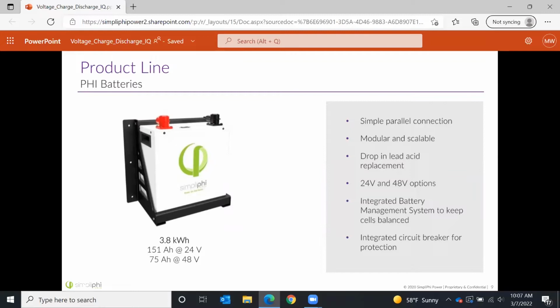It's compatible with a wide range of existing equipment, even older equipment like Midnight charge controllers, Outback charge controllers, even those FX or MX charge controllers, very simple devices that don't need communications. This battery has no external communications built in. It's going to operate very similar to a lead acid battery. You're just going to program set points into the charge controller, and voila. It's got an internal BMS, and additionally a circuit breaker on top, for ease of installation and a bit of added protection, making it simpler to meet code requirements. That's a really nice feature of our batteries that I don't see elsewhere.